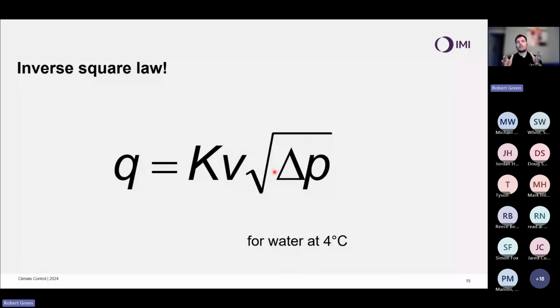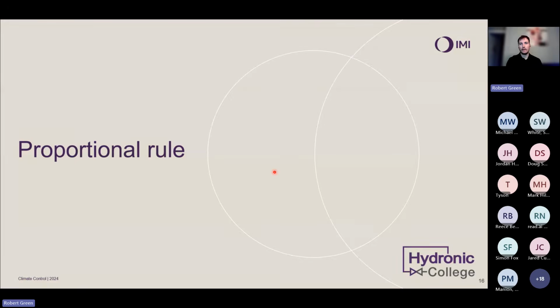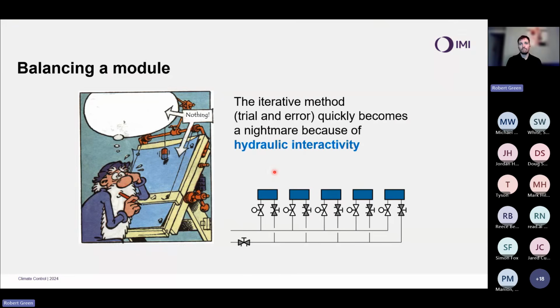So that's some of the relatively straightforward engineering mathematics behind flow versus differential pressure. What I want to look at now is something called the proportional rule. And the proportional rule is something that, if you have ever done any balancing in your careers, or had any influence on balancing, you will have already seen, but you may not realize that you have. If I take a module and I would like to balance it iteratively, i.e. trial and error, it quickly becomes a nightmare.